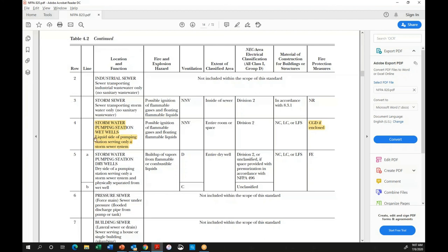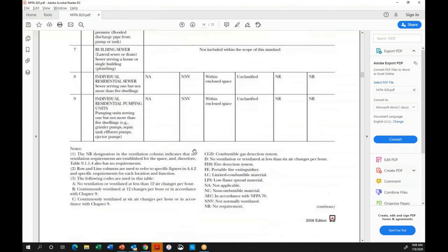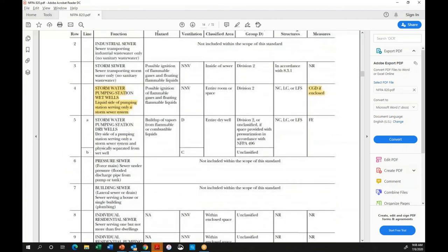It's the liquid side of the pumping station, serving only the storm sewer system. So very specific, and this one's for storm sewer, industrial sewer, and so on. The fire hazard: possible ignition of flammable gases or floating flammable liquids. NNV stands for not normally ventilated, so it gives you that. And right down on the bottom of each one of these pages is a legend for all the different codes. So NNV, not normally ventilated, CGD, combustible gas detection system, and so on.